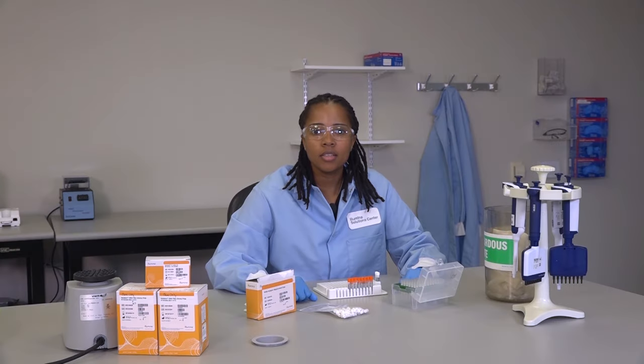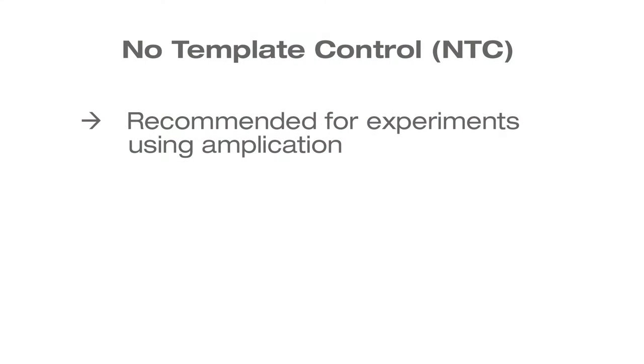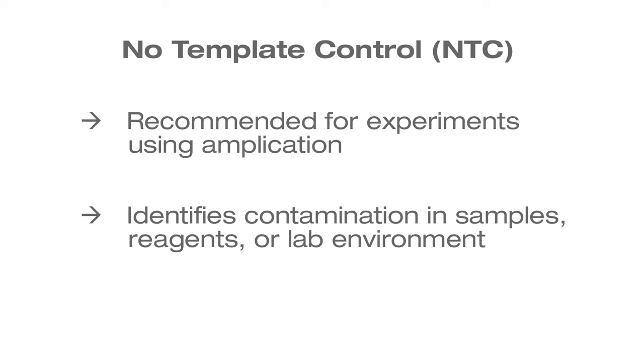It is highly recommended to include a no-template control, or NTC, in experiments using amplification. By including a sample as a no-template control, we can identify contamination in the samples, reagents, or laboratory environment if the NTC generates amplified products. Furthermore, tracking the frequency of contamination can also assist in identifying a root cause of the contamination or preventing an increase in the rate of occurrence.